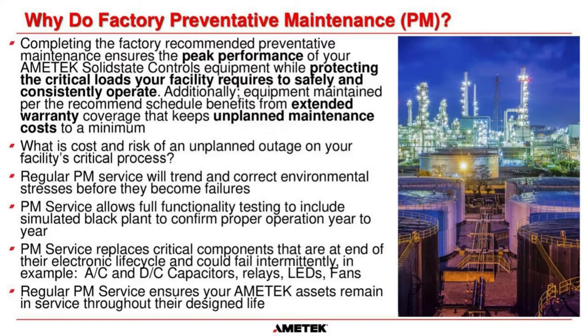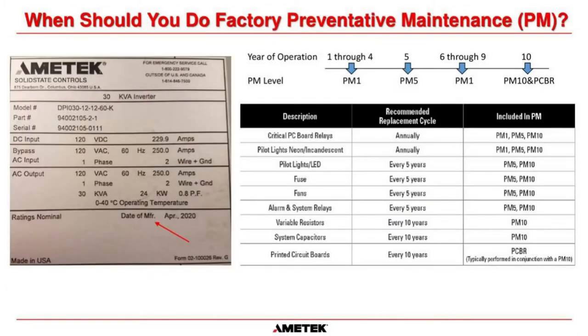PM service allows us to replace critical components at the end of their electronic life cycle that could fail intermittently — system relays, control cards, AC or DC capacitors all have an electronic life cycle. Once reached, they're no longer reliable and should be changed out. Regular PM also extends equipment life; within AMETEK Solid State Controls we have a cradle-to-grave policy — any equipment you purchase, we'll take care of from the day you install it to the day you take it out of service.